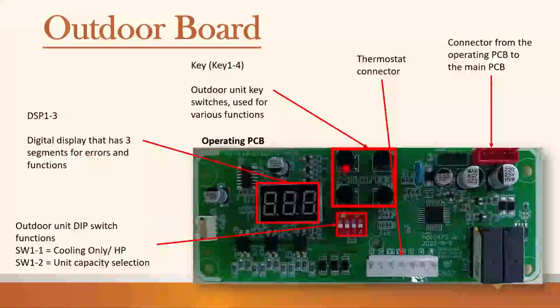Digital display, we can cycle through these with certain buttons, which are key 1, key 2, key 3, key 4. And we have that cheat sheet if you want it, and the installation manual goes through how to adjust those settings by pressing 1, cycling through with 2, entering with 3. I'm not going to go too deep into it because it's easier when you're on site. Oh, and here's that. It's default in heat pump, but if you switch this 1 to on, it's cooling only. So keep that in mind if you do just need cooling only.